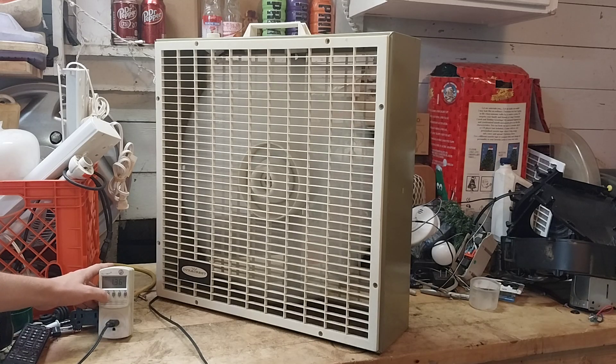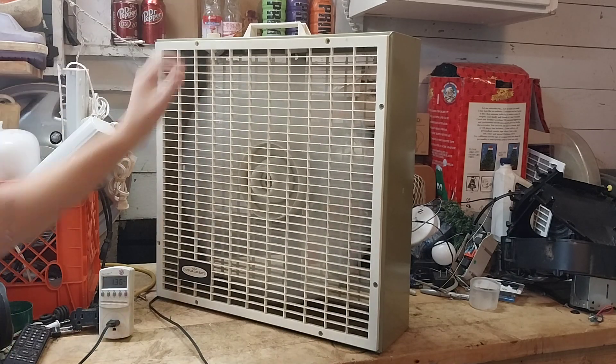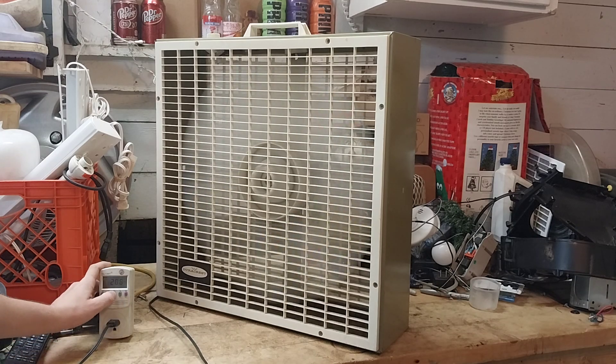On low speed, it's 1.36 amps, 106 watts, and a power factor of 0.64 — so it is shaded pole. We're at just about a little over 120 volts, kind of where it should be. On high speed, the current is 2.8 amps, 206 watts, and a power factor of 0.61.